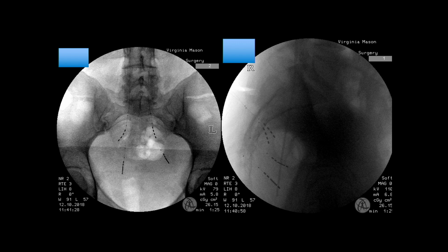This one is a ghost lead. This one's a ghost lead. So I tried to take them out when she got pregnant. She needed an MRI for some reason. We're going to talk about taking the leads out because a ghost lead is when you take it out, I don't know if any of you have had that experience where you pull, and all of a sudden it gives and you've got your casing in there and you've got your wires hanging out, right? So that's a ghost lead.